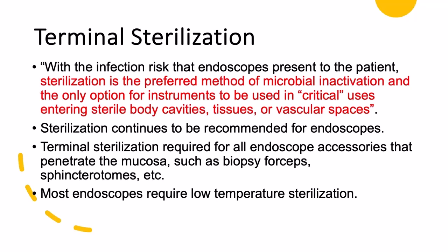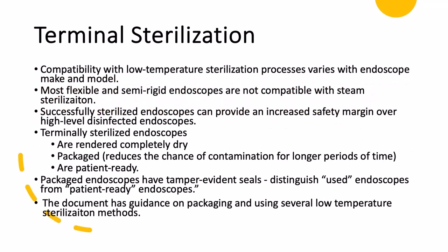And most endoscopes today require low-temperature sterilization, but we are seeing some that can be steam sterilized. Compatibility with low-temperature sterilization will vary with the endoscope make and model. Most flexible and semi-rigid endoscopes are not compatible with steam, but successfully sterilized endoscopes can provide an increased safety margin over high-level disinfected endoscopes. That's because when they're sterilized, they're completely dry, they're packaged, and they're patient-ready. They also have a tamper-evident seal that distinguishes used endoscopes from patient-ready, and the document has guidance on packaging and using several low-temperature sterilization methods.